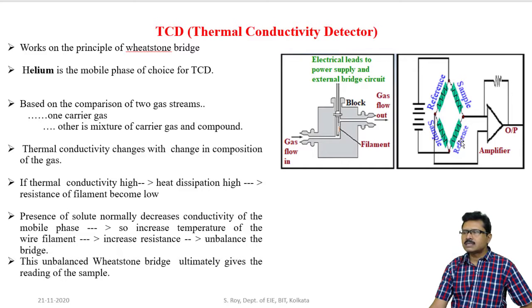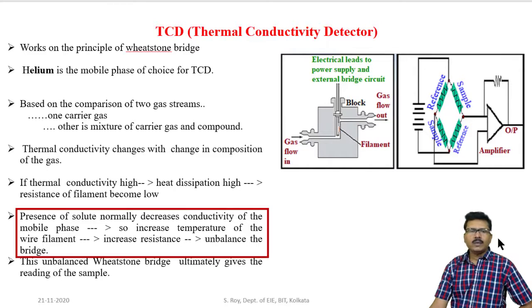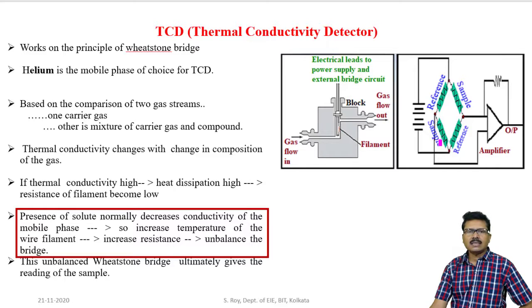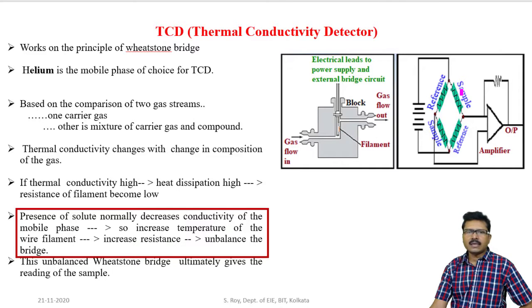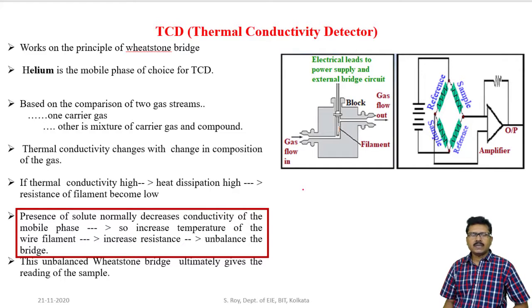The reference gas is allowed to pass through two opposite arms of the Wheatstone bridge, and through the other two opposite arms, carrier gas with sample is allowed to pass. When no sample gas is present, the bridge will be balanced because all four arms are exposed only to carrier gas. When sample gas is present with the carrier gas and passes through those opposite arms, conductivity is reduced — presence of solute normally decreases conductivity of the mobile phase. When surrounding conductivity decreases, heat dissipation decreases and temperature of the resistance increases.